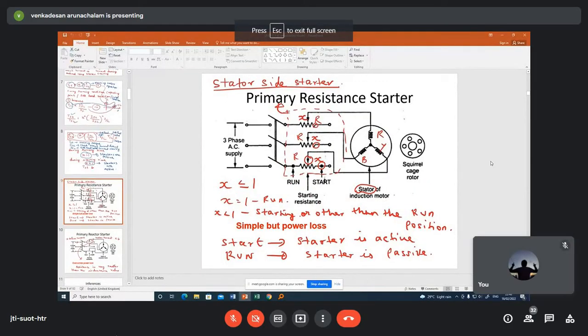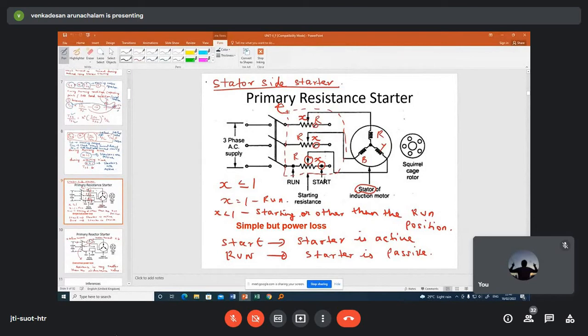The stator starter, the first one, the primary resistance starter. Here some set of resistance are added in series with the stator winding. It is a very simple starter. During starting time maximum resistance is added, and during running time the resistance is all cut out, and minimum resistance or zero resistance remains in the stator winding.